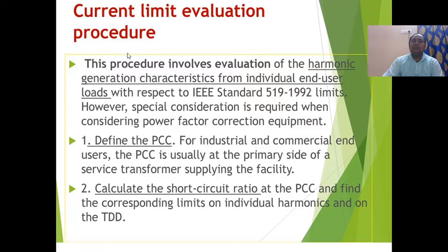Current limit evaluation procedure. This procedure involves evaluation of harmonic generation characteristics from individual end user loads with respect to IEEE standard 519-1992 limits. However, special consideration is required when considering power factor correction equipment.